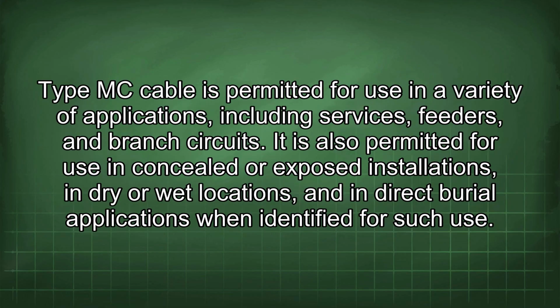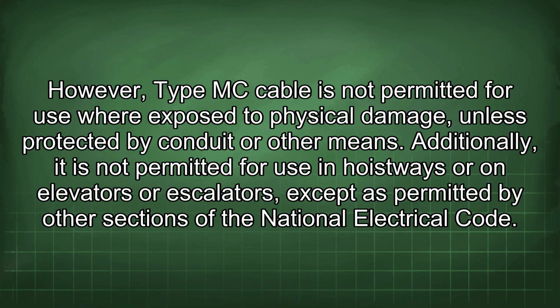Type MC cable is permitted for use in a variety of applications, including services, feeders, and branch circuits. It is also permitted for use in concealed or exposed installations, in dry or wet locations, and in direct burial applications when identified for such use. However, Type MC cable is not permitted for use where exposed to physical damage unless protected by conduit or other means. Additionally, it is not permitted for use in hoistways or on elevators or escalators except as permitted by other sections of the National Electrical Code.